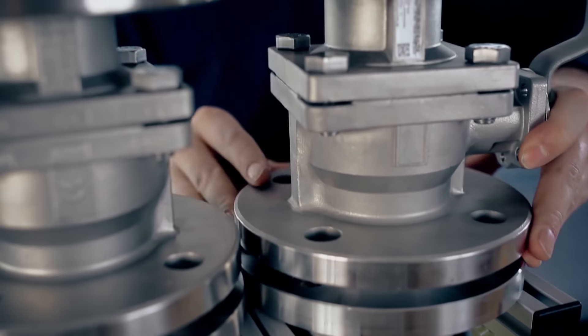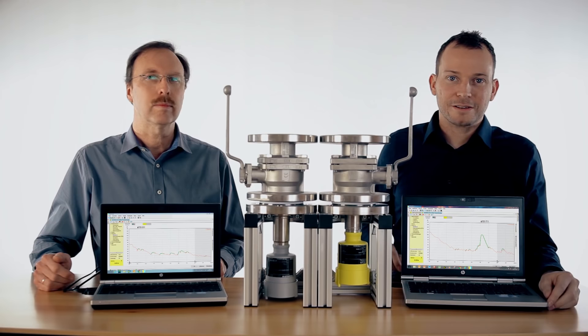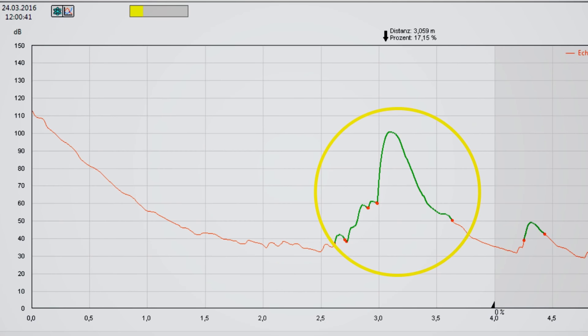On this side we also put a ball valve on the top of the Vega Pulse 64. We have a look on the echo curve. You see there is a slight change in the signal but there is not a big problem for the sensor. He gets not false reflection and he still has a very nice product echo to measure.